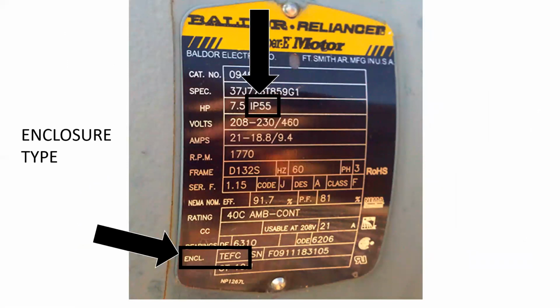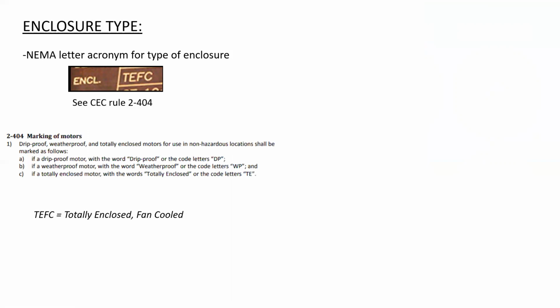And finally, enclosure type. This one has 2 ratings that both refer to the enclosure type. The first one is IP55, the second one is TEFC. The first one we're going to look at is the TEFC. This is a NEMA letter acronym for the type of enclosure. We can find a number of these listed in the Canadian Electrical Code, Rule 2404. It tells us that the standard types of motor enclosures are drip-proof, weatherproof, and totally enclosed, and for this particular motor, the TEFC indicates fan-cooled.